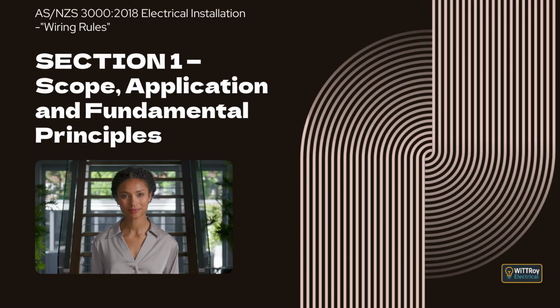Clause 1.5.7, Basic and fault protection by use of extra low voltage. This clause explains how SELV systems, or PELV systems, can be used to provide both basic protection and fault protection, but only when certain conditions are met. First, the nominal voltage must never exceed the limits for extra low voltage. That means no more than 50 volts AC, or 120 volts ripple-free DC, even if the supply is arranged in different ways. Second, all circuits must be electrically separated from each other, and separated from any higher voltage circuits. Third, live parts of SELV circuits must never be connected to earth, or connected to protective earthing conductors, or to live parts from any other circuit.